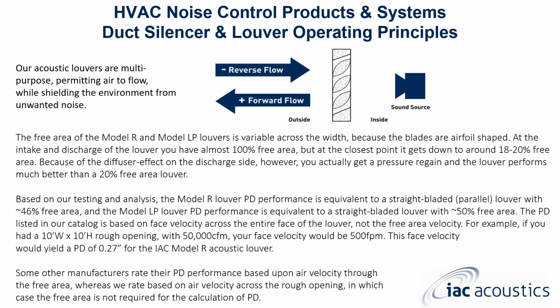So for example, if you had a 10-foot wide by 10-foot high rough opening at 50,000 CFM, your face velocity would be 500 feet per minute. The face velocity here would yield a pressure drop of roughly 0.27 inches water gauge for the IAC Model R acoustic louver. So some other manufacturers rate their performance based upon air velocity through the free area, whereas we rate based on air velocity across the rough opening, in which case the free area is not required for the calculation of pressure drop. I will say this, a lot of people design a free area first.